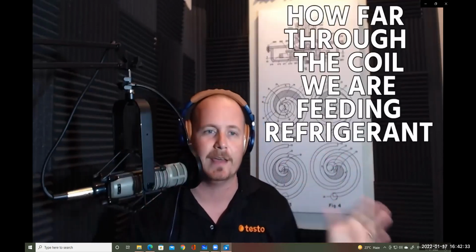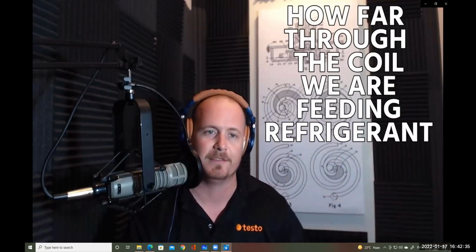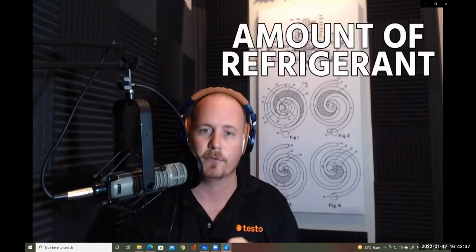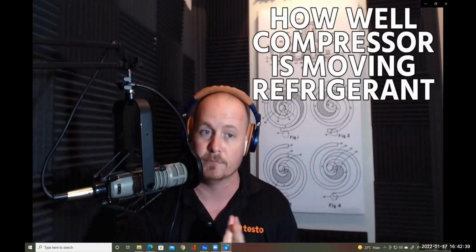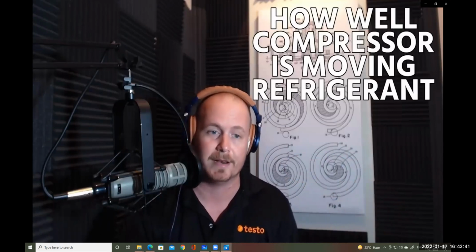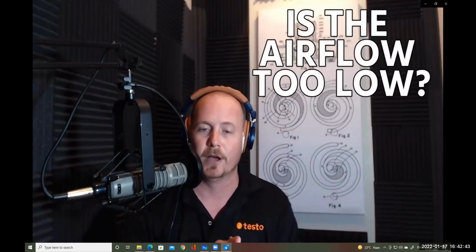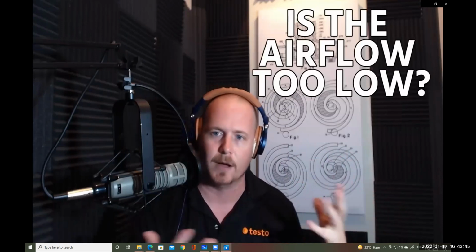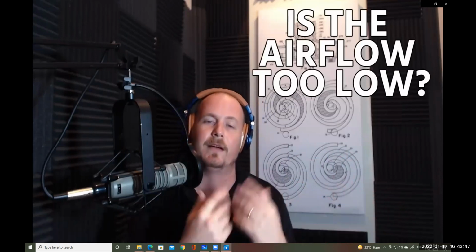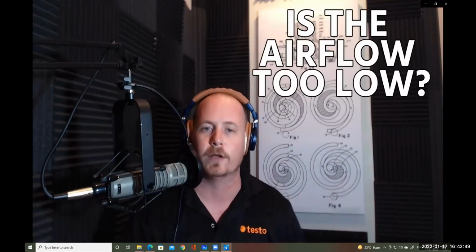Now, everything in the air conditioning and refrigeration system affects everything else. So the amount of refrigerant, how well the compressor is moving that refrigerant, how well it's circulating it, if it's compressing properly, whether or not your condenser coil is dirty or has problems, or whether or not the airflow moving over that evaporator coil is too low. There's all kinds of factors that impact how an evaporator coil absorbs heat. But remember that when we're attempting to cool something, that really is the point.